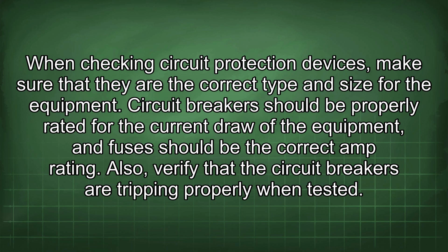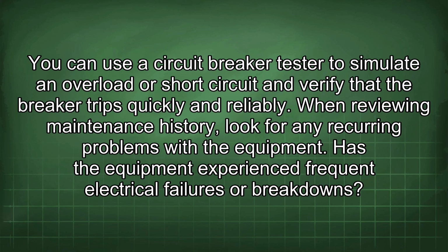When checking circuit protection devices, make sure that they are the correct type and size for the equipment. Circuit breakers should be properly rated for the current draw of the equipment, and fuses should be the correct amp rating. Also, verify that the circuit breakers are tripping properly when tested. You can use a circuit breaker tester to simulate an overload or short circuit and verify that the breaker trips quickly and reliably.